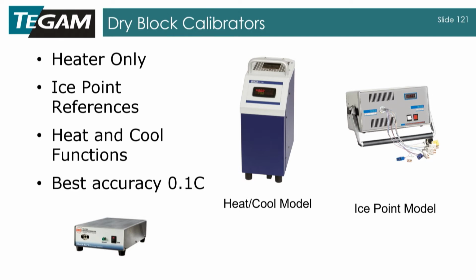And there are also ice point references. If you're really just trying to zero probes, instead of having to fool around with crushed ice and make a bath, you can use an ice point reference. The best accuracy you can get is about 0.1 C. You can get half a degree C or 1 degree C with cheaper instrumentation, but about the best you're going to get out of something like this is about 1/10 of a degree C.